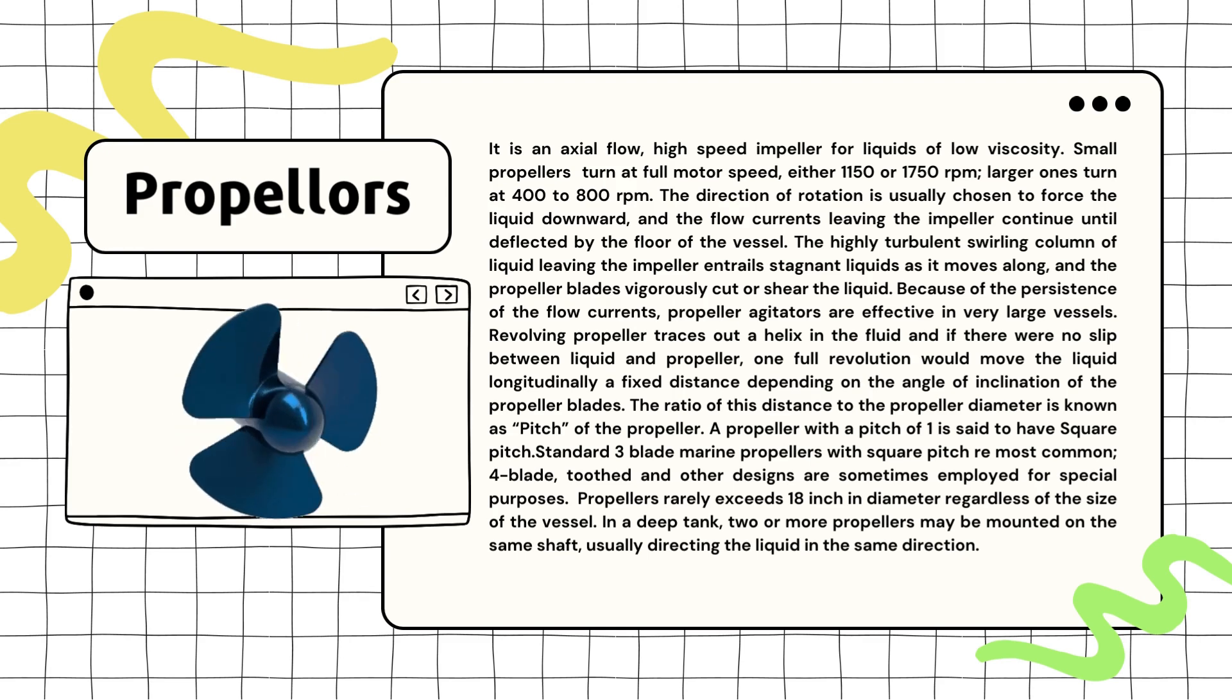The swirling flow of this liquid continues until it hits the bottom of the container. As this swirling liquid moves along, it pulls the stagnant liquid around it. The blades of the propeller also chop up or shear the liquid into small pieces. These propeller agitators are really effective in very large containers because the swirling flow persists for a longer period.